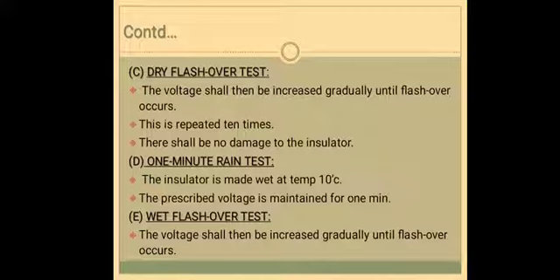The next is the 1 minute rain test. In this, the insulator will be sprayed throughout the test with artificial rain drawn from a source of supply at a temperature within 10 degrees Celsius of the ambient temperature of the neighborhood of the insulator. The rain will be sprayed at an angle of 45 degrees on the insulator at a prescribed rate of 3 mm per minute, and the prescribed voltage will be retained for 1 minute.